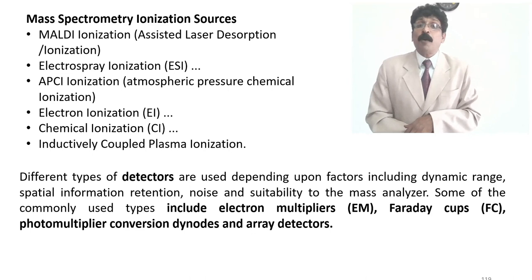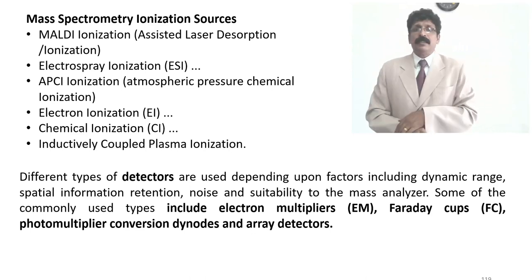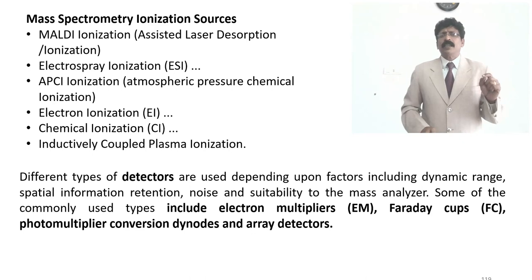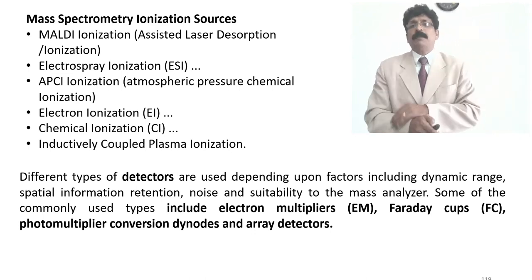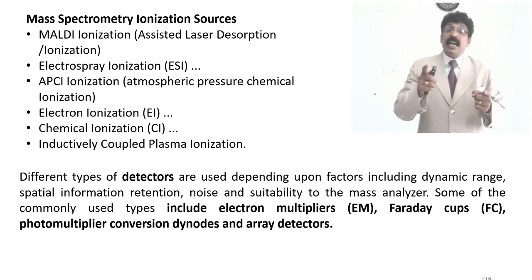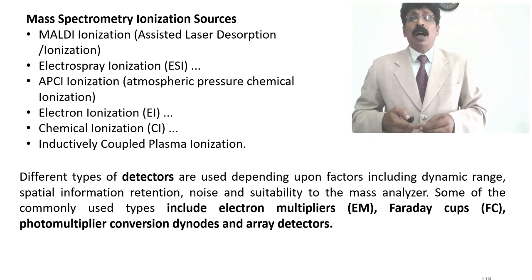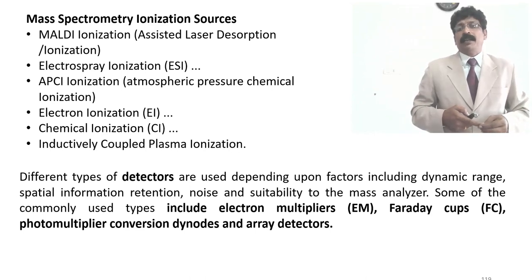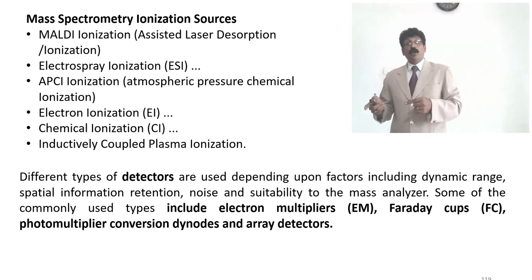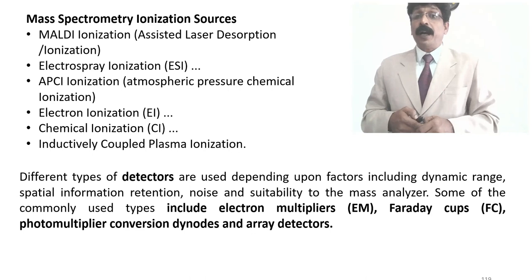Different types of detectors are used depending on factors including dynamic range, spatial information retention, noise, and suitability to the mass analyzer. Commonly used detectors include electron multipliers — which amplify and multiply the ions to produce a measurable current impulse identifying the mass number — as well as Faraday cups, photomultiplier conversion dynodes and array detectors. These amplify and identify the mass of the compound clearly.